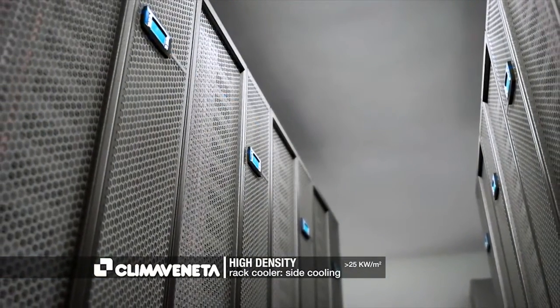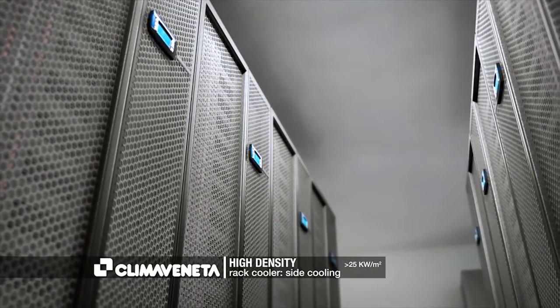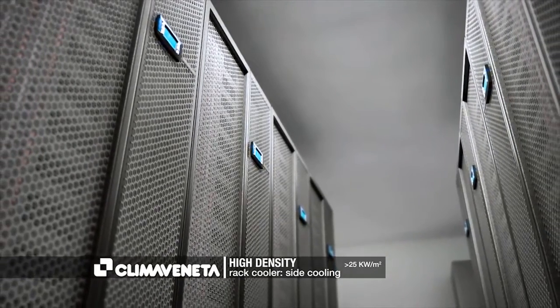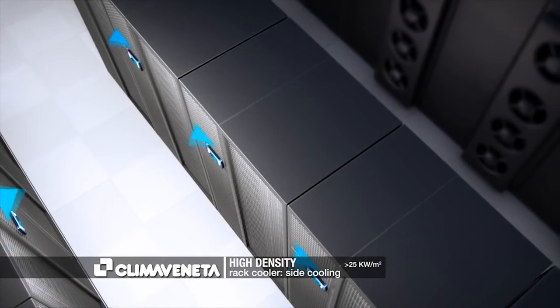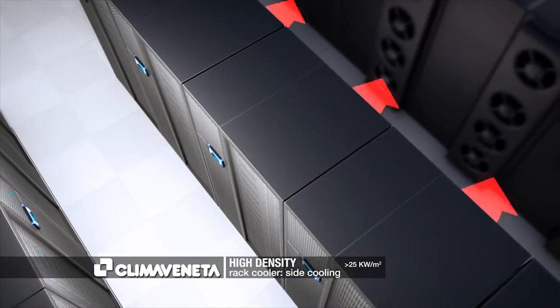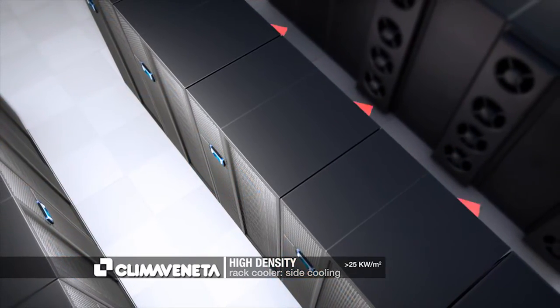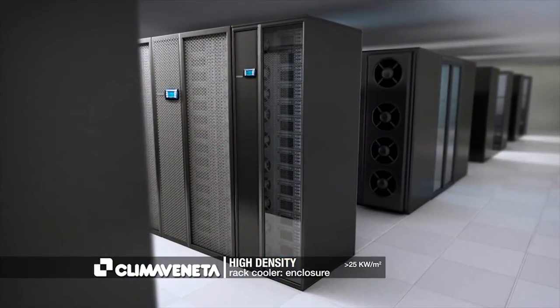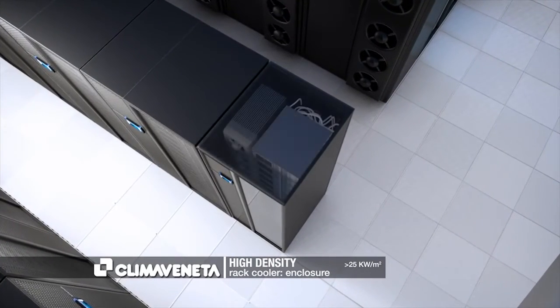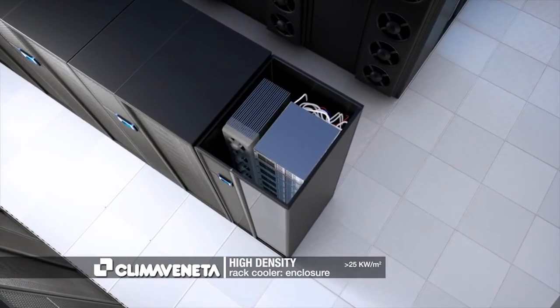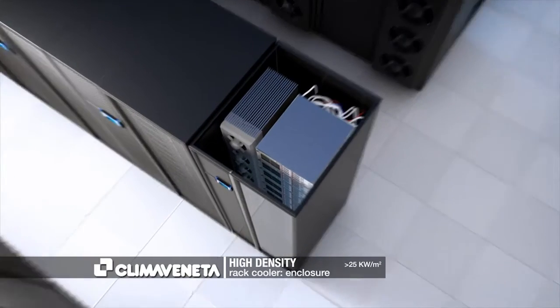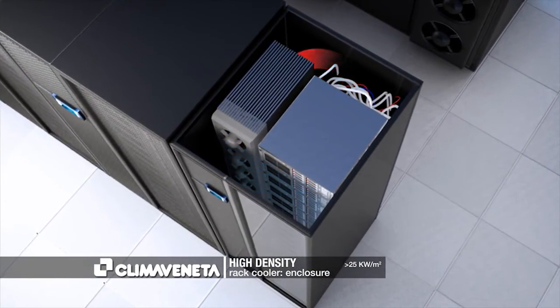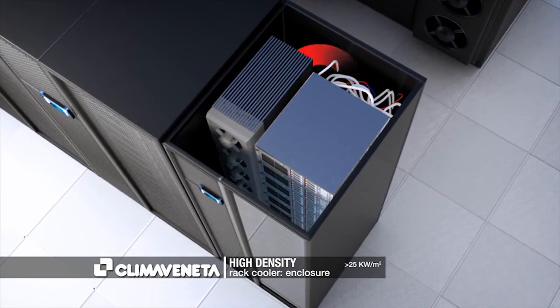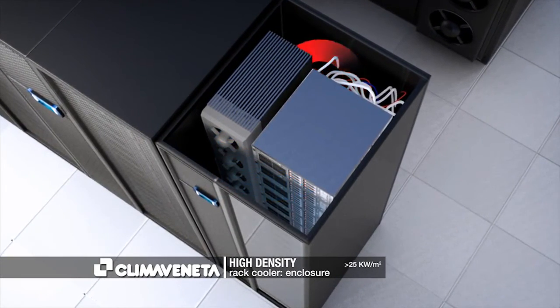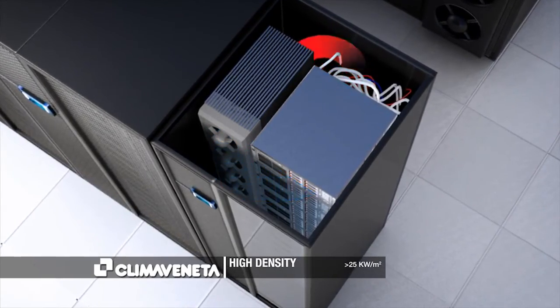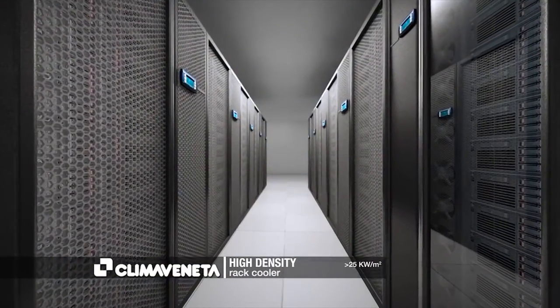Rack coolers are high-efficiency cooling elements that can be used in the most critical situations. Each rack cooling unit cools a part of the cold corridor or even one single rack. A special version of the rack cooler, called enclosure, provides cooling inside the rack at the highest efficiency. In this way, servers are autonomous and receive the right amount of cooling regardless of their position in the data center. These units can be adapted both to chilled water and direct expansion versions.